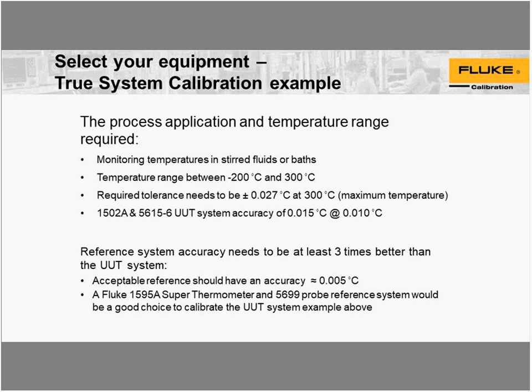Okay, so another thing we need to look at is that the reference systems you're using need to be at least 3 times better than the UUT system. So for this particular item at 0 degrees, we would like to have it at least 0.005 degrees, 5 millidegrees. So what we're going to use is a Fluke 1595A super thermometer, 5699 thermometer probe, which is a platinum resistance thermometer. The system would have a combined uncertainty of 5 millidegrees.